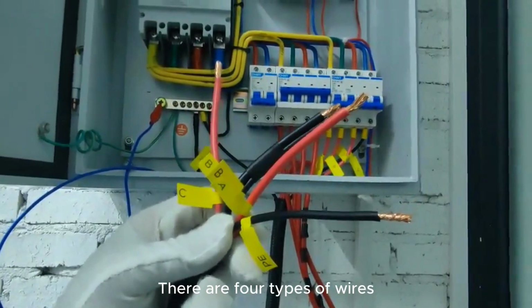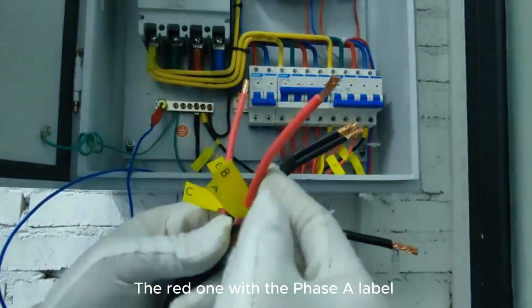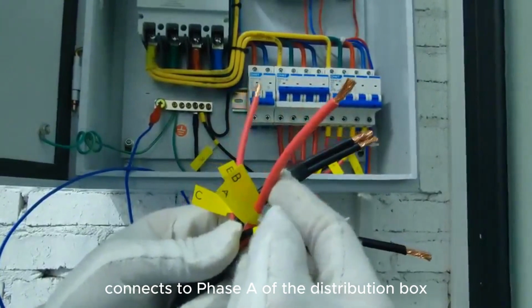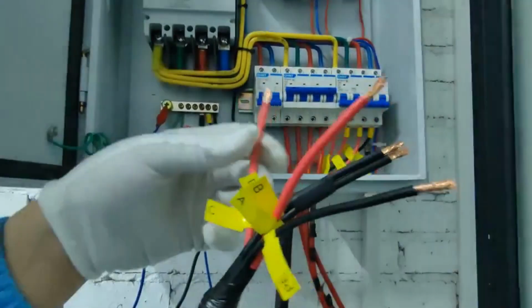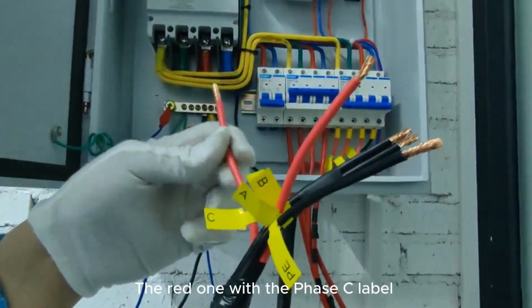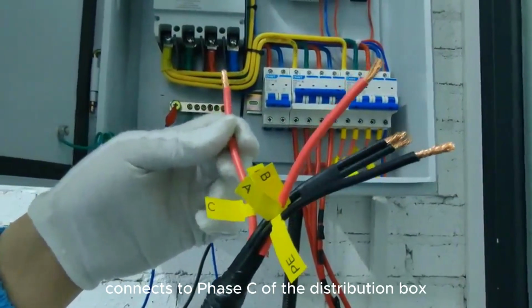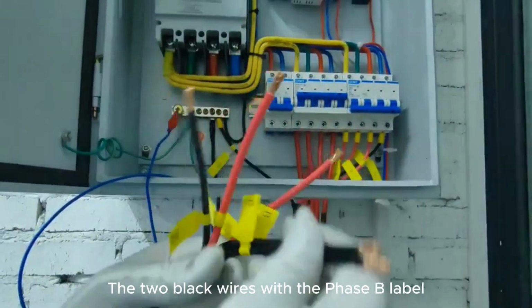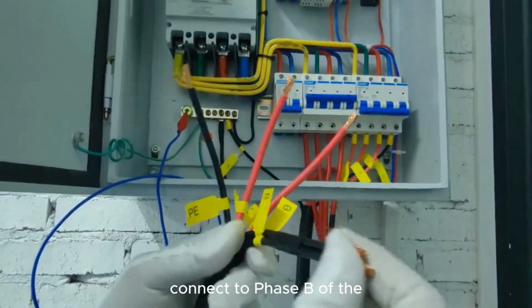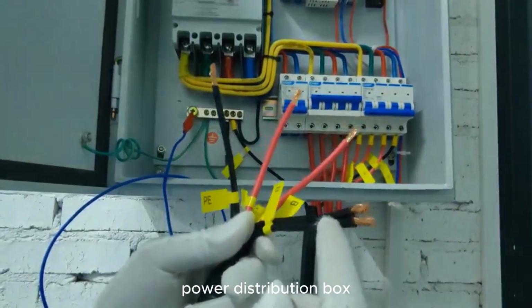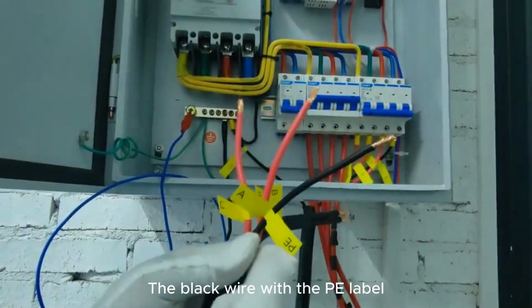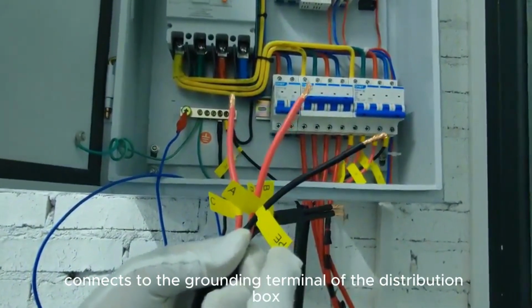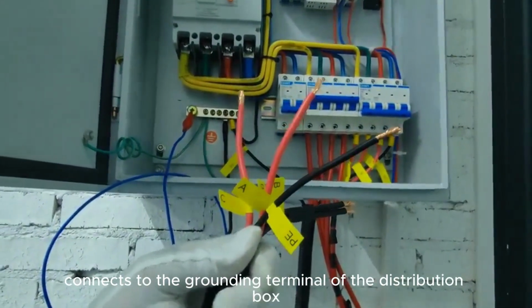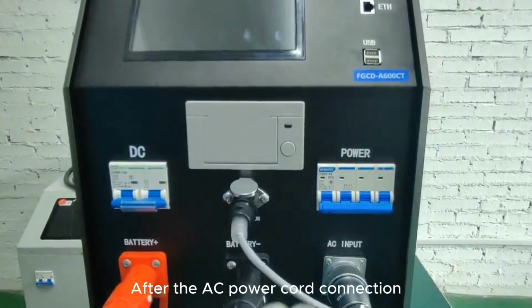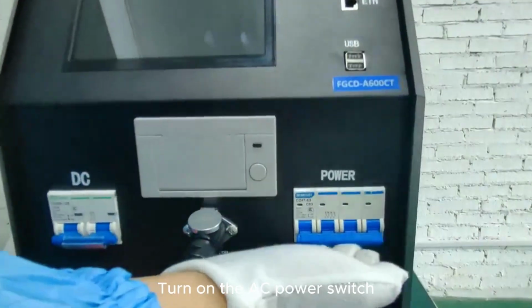There are 4 types of wires. The red one with the phase A label connects to phase A of the distribution box. The red one with the phase C label connects to phase C of the distribution box. The 2 black wires with the phase B label connect to phase B of the power distribution box. The black wire with the PE label connects to the grounding terminal of the distribution box. After the AC power cord connection, turn on the AC power switch to power on the tester.